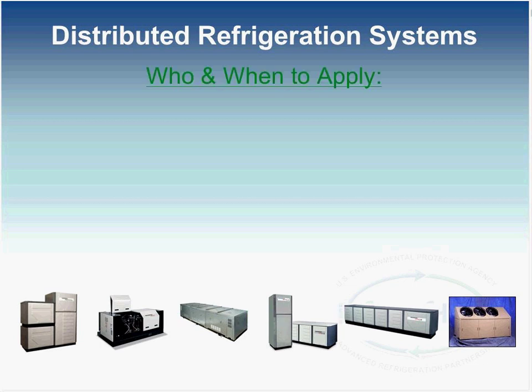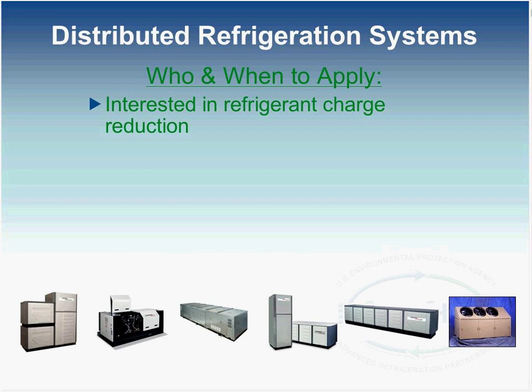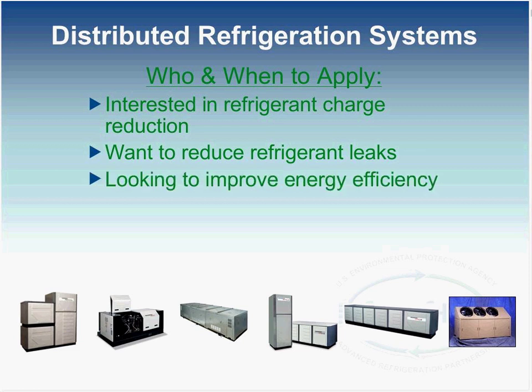So in summary, on the distributed side, who should be looking at these types of systems and when would you want to put these in the store? One, obviously, if you're looking to reduce your refrigerant charge as compared to a centralized system. And then, of course, if you're interested in reducing the number of leaks, by having fewer braze joints through the store and a lot less piping, the potential for leaks is reduced accordingly. And then, like we just discussed, the energy performance of the system as a whole: having distributed type systems, you can realize some energy benefits depending on how these units are applied and located.